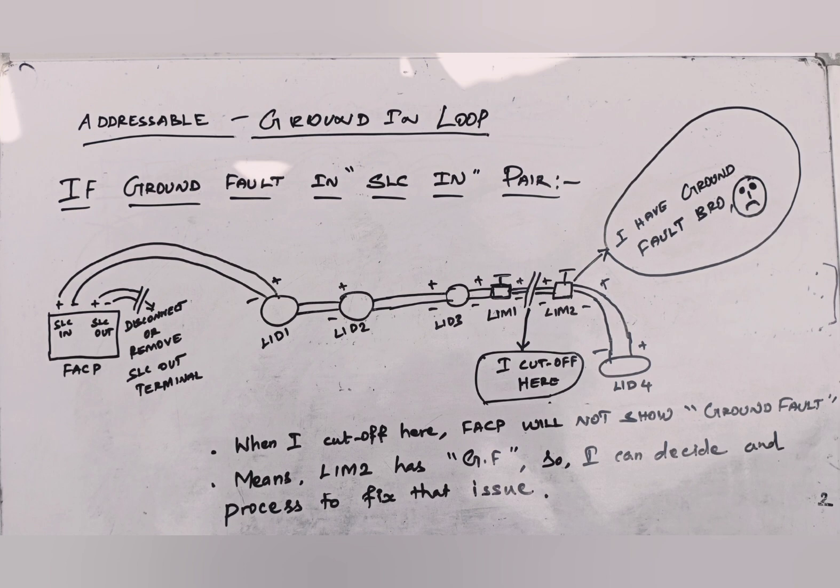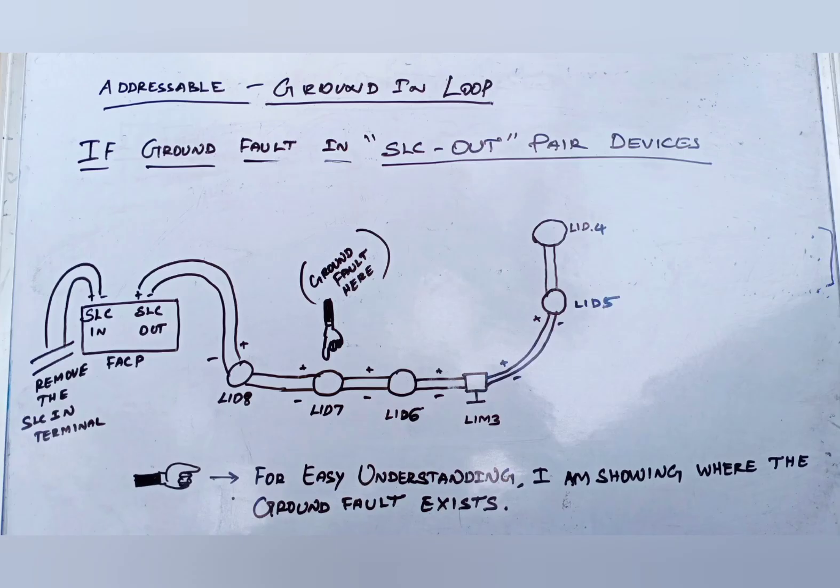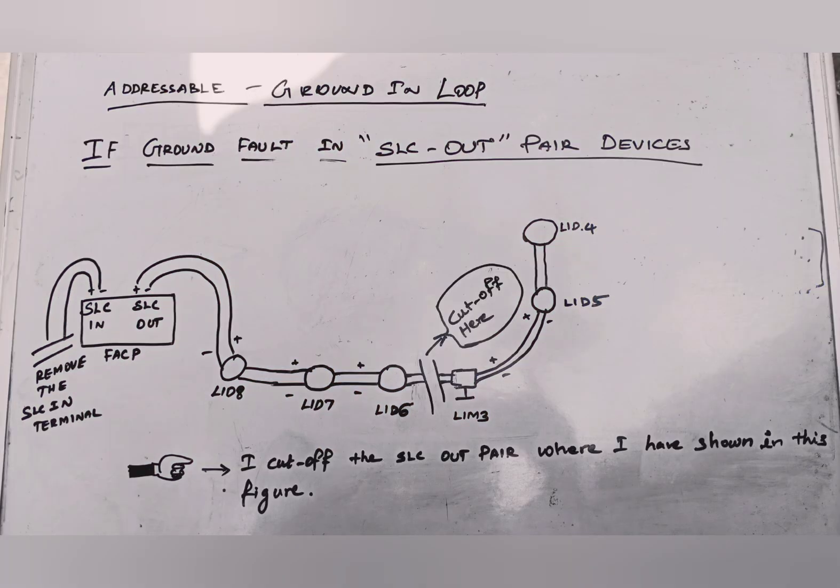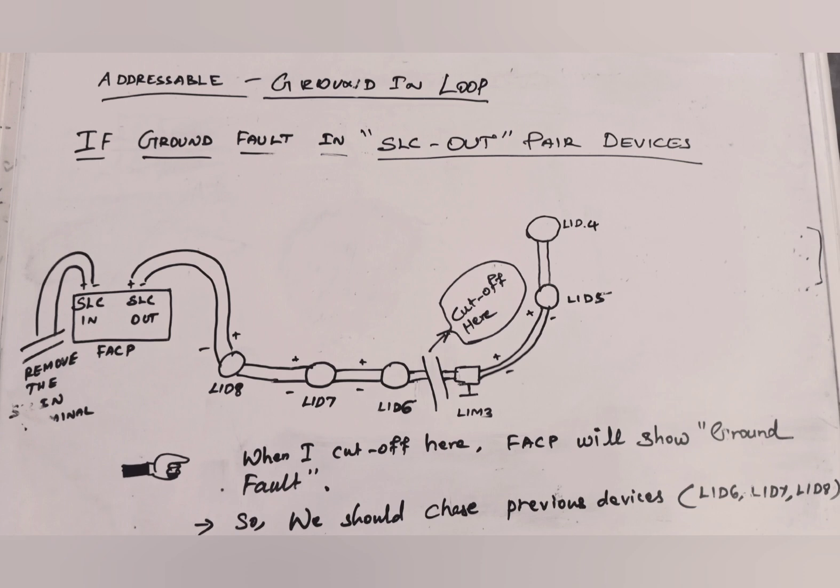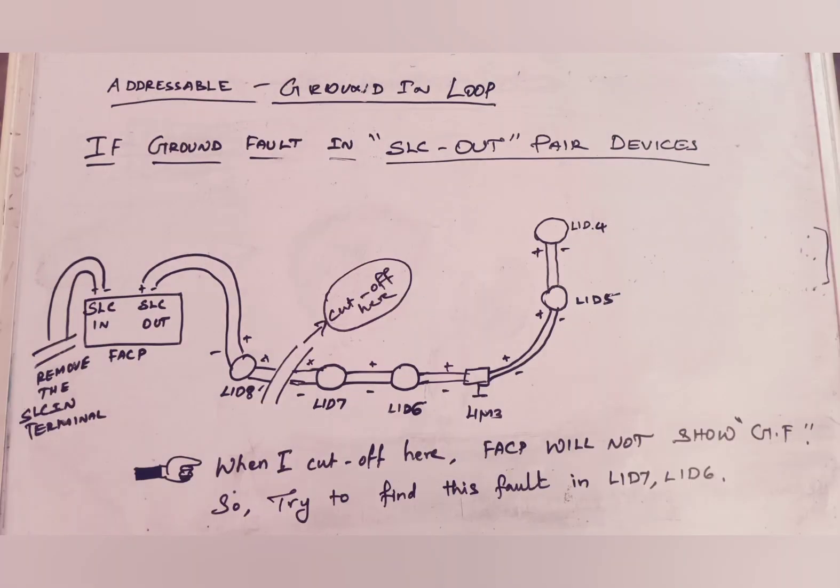Vice versa, when you will make troubleshooting for ground fault in SLC out pair wire, you need to follow the same way what we have done in SLC in pair wire troubleshooting for ground fault.